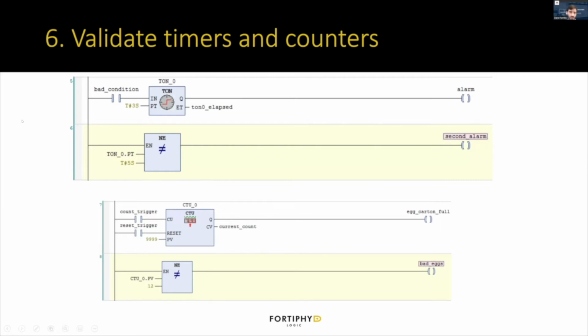And so here is a very simple example of how you might do this in CODESYS. I have a timer block up there at the top, and just have a double check to see what the preset value is for the timer, to verify whether or not it was the exact time that we set. So it looks here like the timer block has a preset value of 3 seconds, but our check has a preset value of 5 seconds. And so you might want to raise an alarm to say that the double check found the preset value was wrong. Maybe someone modified it and they didn't update it in both places. If that's the attacker just trying to play around with the code and mess with something, it might help them check. The more complicated case of the preset values coming from some other calculation can also provide some double checks of whether or not the value is right.